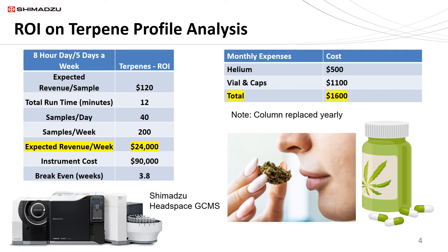The table presents an analysis time of 12 minutes, which could be increased based on the number of terpenes being analyzed. It has been reported there are over 5,000 terpenes in nature and 200 in cannabis, although most profiles analyzed contain less than 20. Revenue is typically in the range of $120 per sample. At 200 samples per week, the revenue will be $24,000 per week, and the break-even point for the instrument is typically less than one month. The most prominent consumable is helium at $500 per month. Adding vials and caps increases expenses another $1,100 for a total of $1,600 per month. Because the sample is very clean, the column would only need to be replaced yearly.